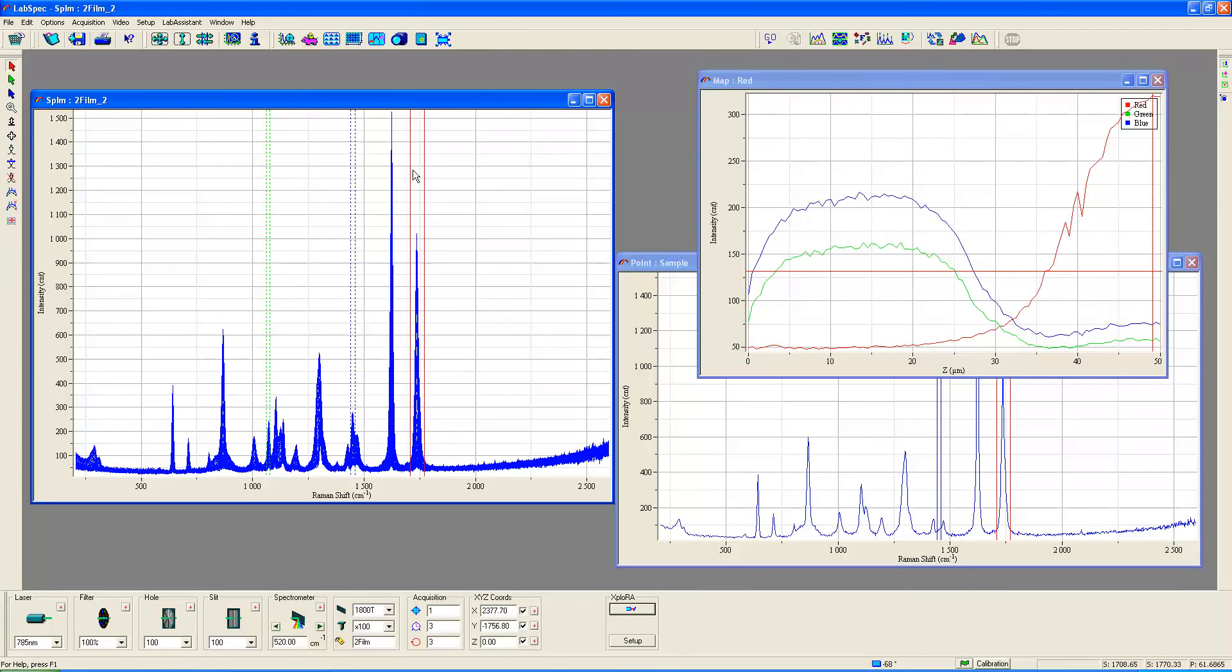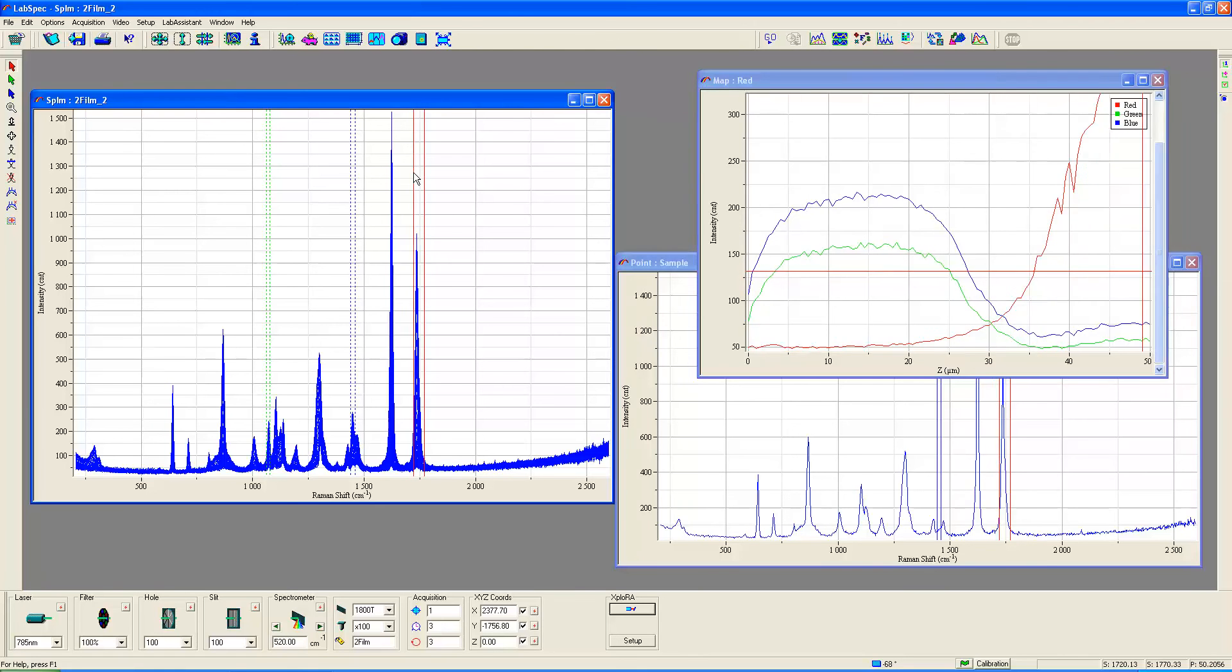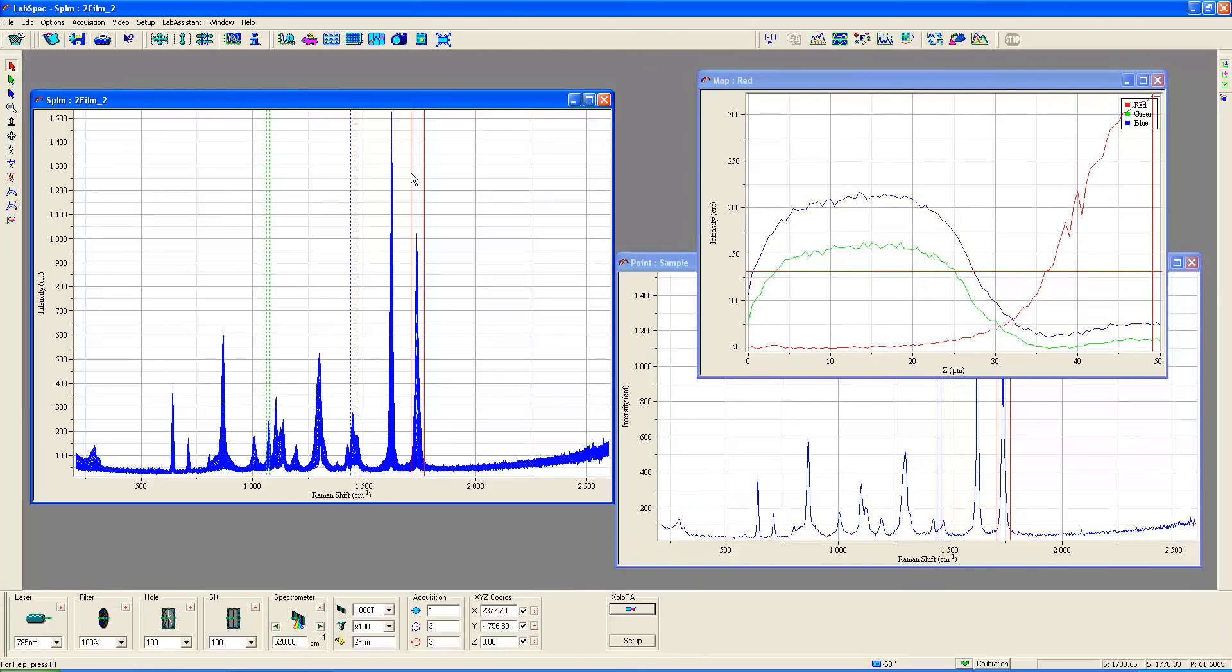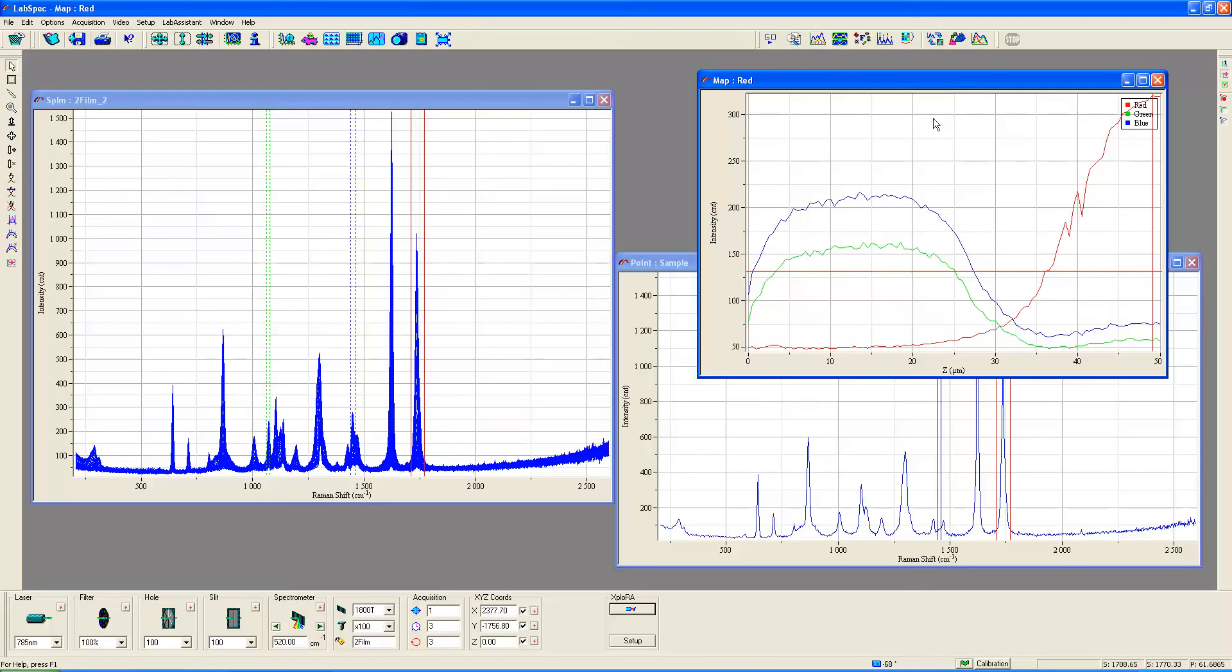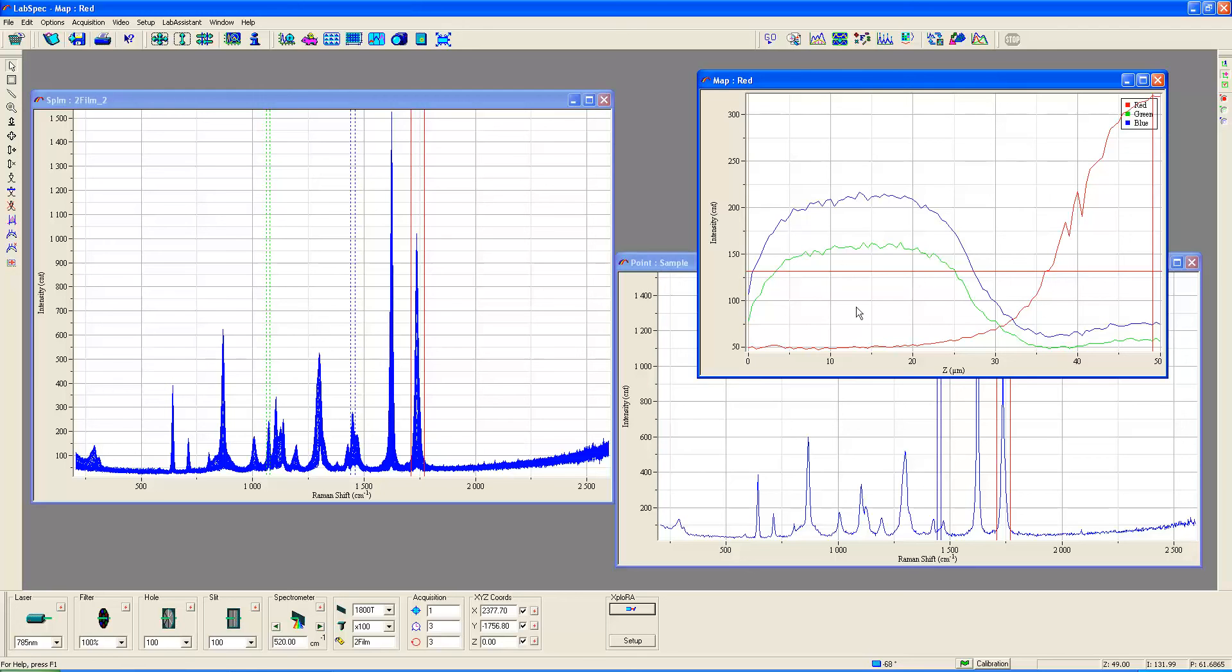What I've done here is I've bracketed the blue and the green around polyethylene raman bands and I'm moving the red bracket essentially around the carbonyl band of the polyethylene terephthalate. As I did that you can see that the response of this profile for the counts was changing as I moved that bracket. These are basically the integrated intensities of these peaks between the green, the blue and the red cursors.